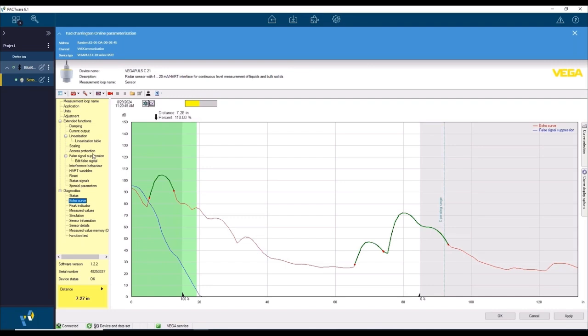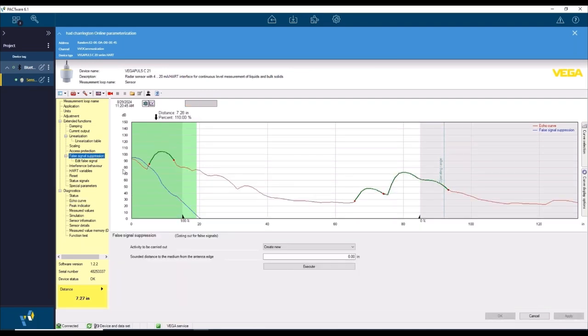So step one, you select the false signal suppression. And now you're going to select create new. Your options are create new, extend, or delete all. But we're going to do a create new. Now next, you're going to put in the distance to the bottom of your lift station. So you click on the lift station echo, or you can pull out a measuring tape and measure it however you choose to do it, electronically or mechanical. So it says here place, that's distance. So it's 78.39 inches down is my level. So I come here and I'm gonna put in 78.39.